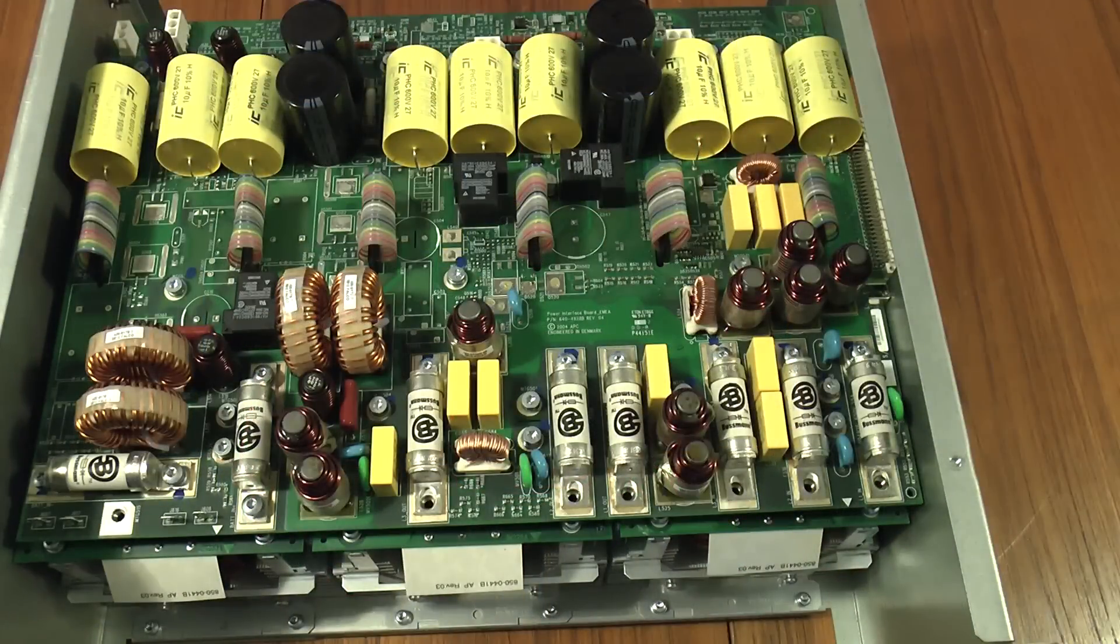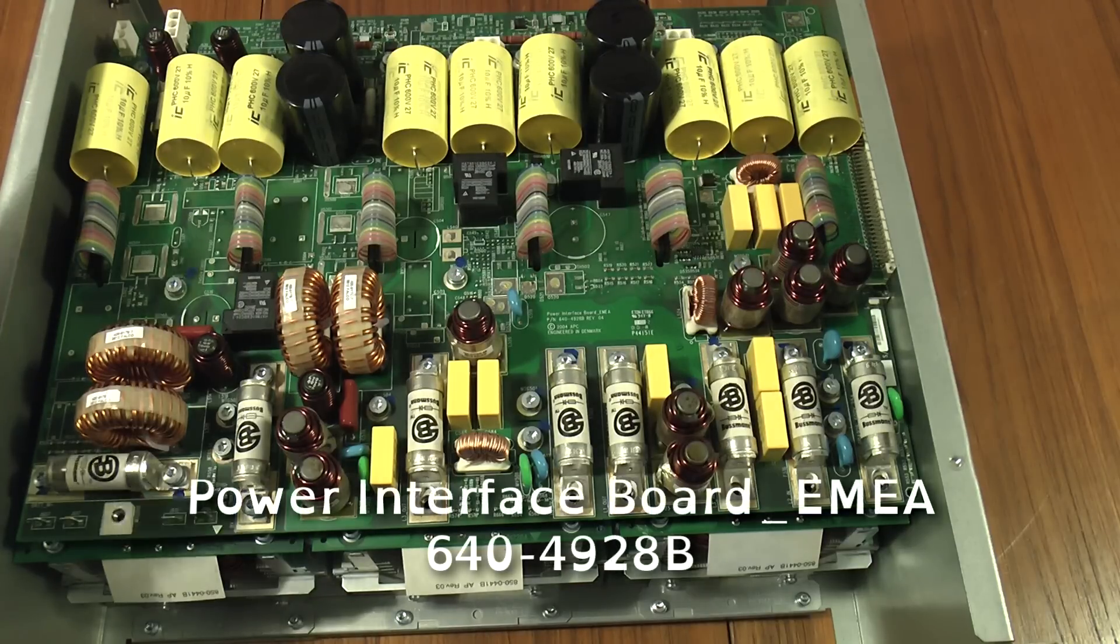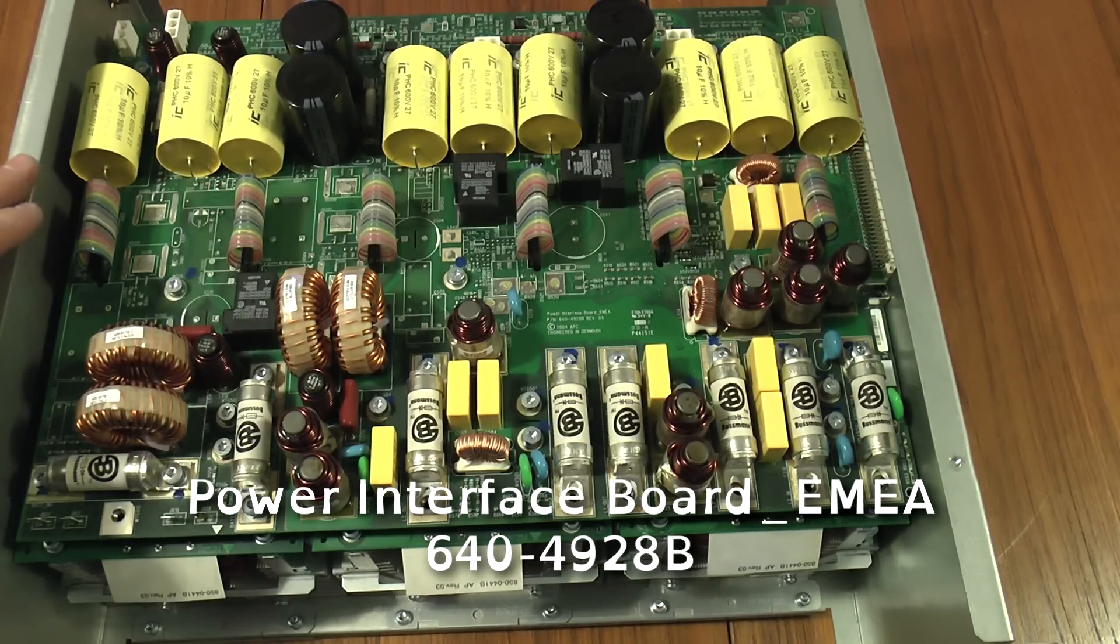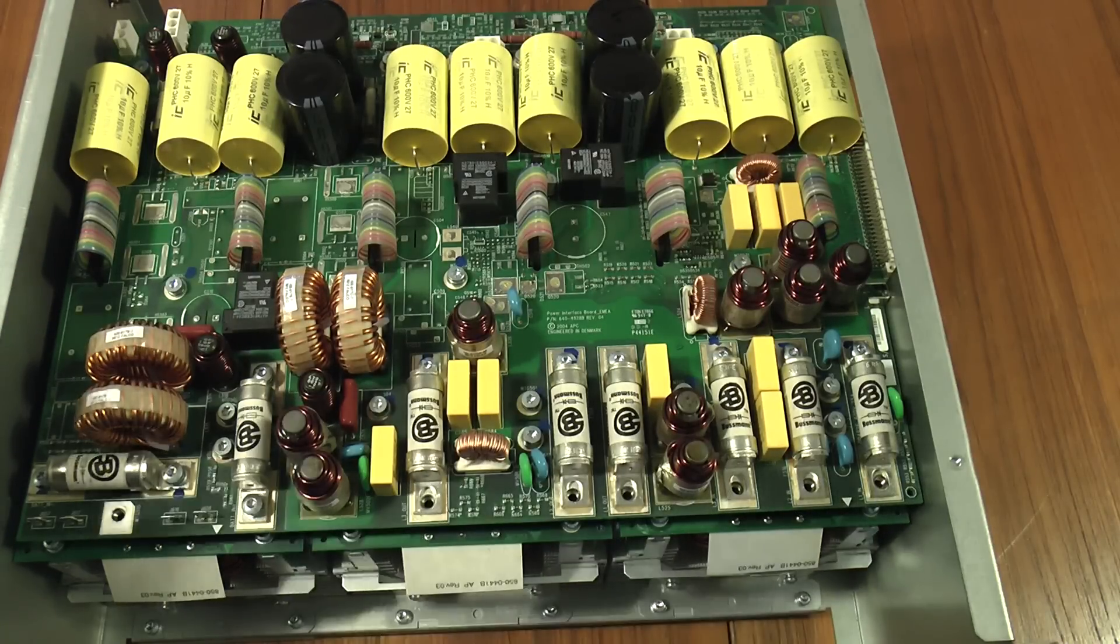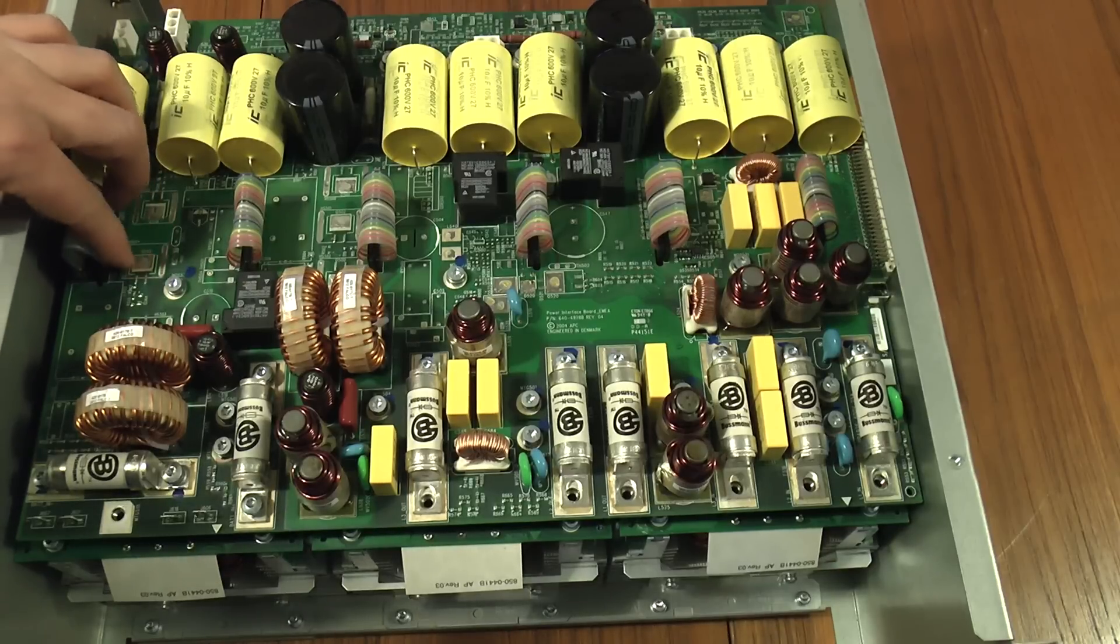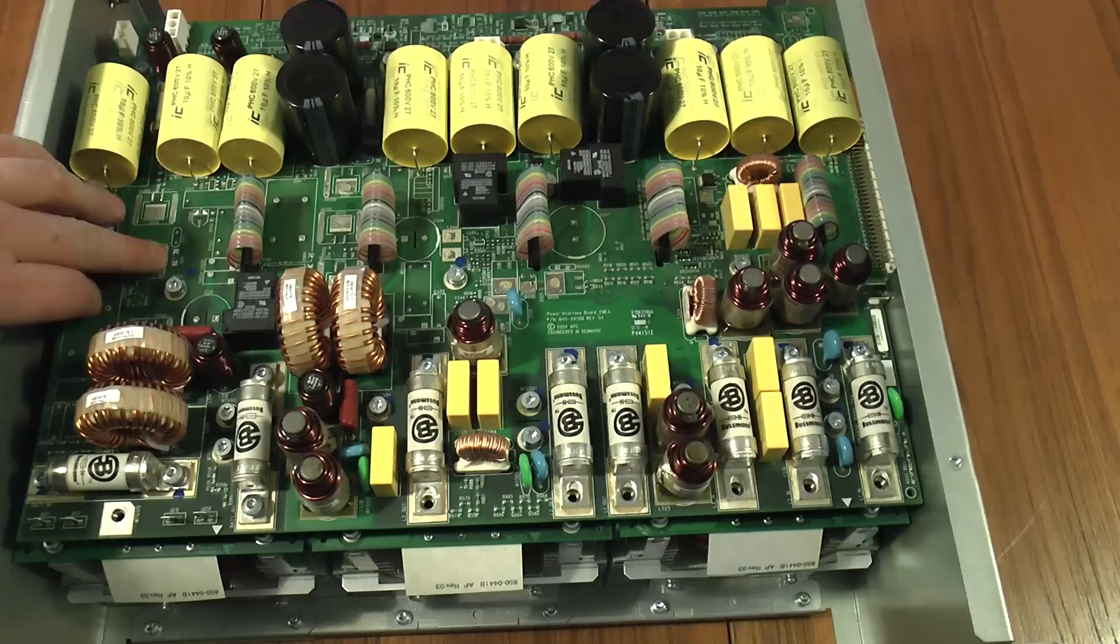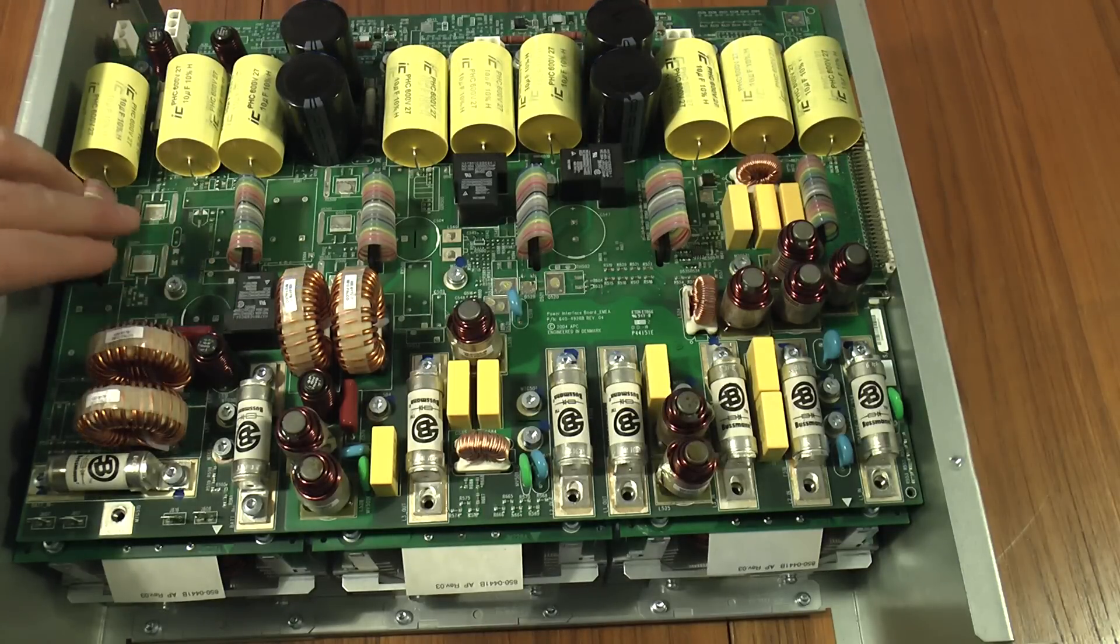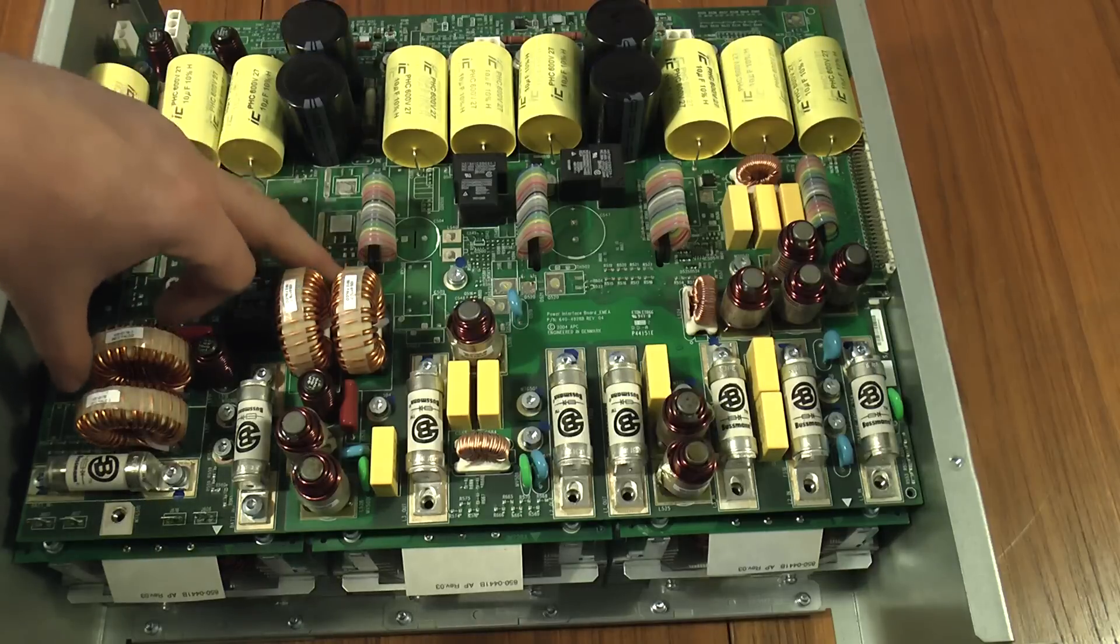That's the brains of the outfit dealt with. Onto the brawn. This is one of the power modules. This is the secondary power module. If it was a SmartUPS VT20, this power module wouldn't be in there. It would just be the other one. You can see here where those heatsinks would appear. On the other board they're there. On this one that's just blanked off. But you can see where you'd have those heatsinks sitting over the top of the power transistors here.